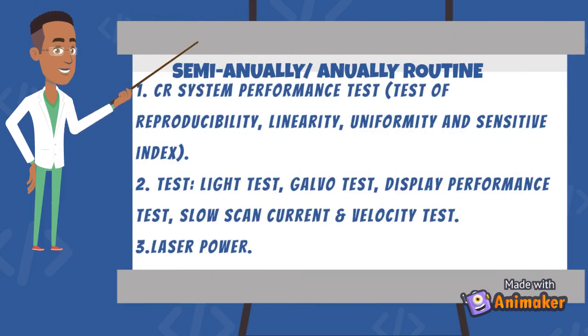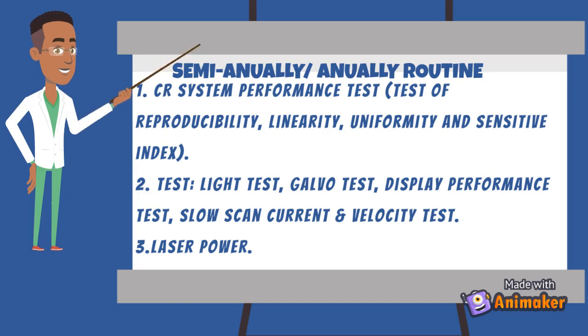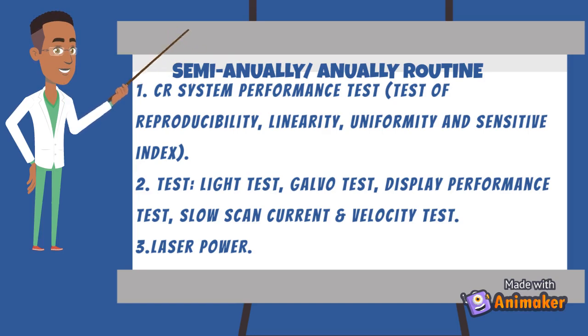Semi-annually or annually, routine tests can also be conducted to perform the CR reader system performance test, light test, slow scan current and velocity test, laser test, galvo test, and finally the display performance test of the CR reader system.